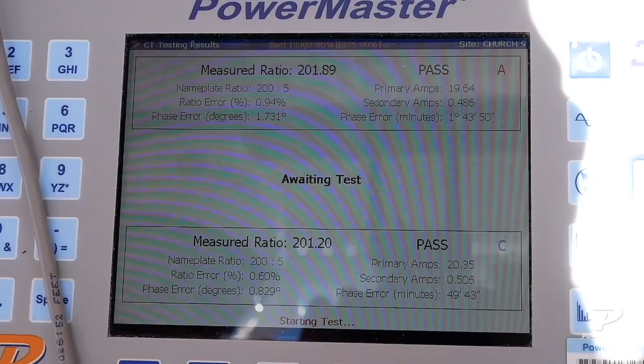It was corrosion. It was the grease, and we've talked about that in another one, but I'm going to talk about it again. It was all of the grease that was in there. That just becomes a trap for everything, right? So we had the grease, then we had the corrosion at the test switch, actuating those switch handles. Actuating both the return and the shunt helped. And then last but not least, when we were really close, it was going to the screws behind the meter on B phase. We loosened and tightened those screws a couple of times. Now we've addressed the corrosion issue, and it pulled in and got tested correctly.